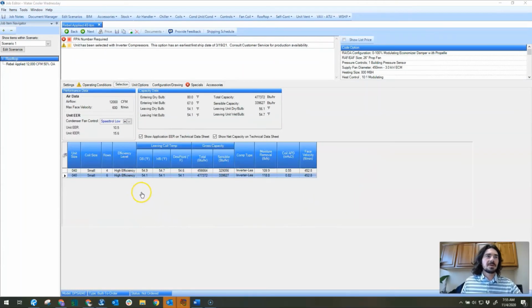And on the selection tab, it shows us the combination of condenser and coils. So we got a 4-row option and a 6-row option. I'm just going to leave it on the 6-row option, showing a 54-degree leaving air temp off the coil. Up here, we're showing a leaving temperature of 56. This is leaving the unit, so this accounts for fan heat. So it's a nice number to have in mind.